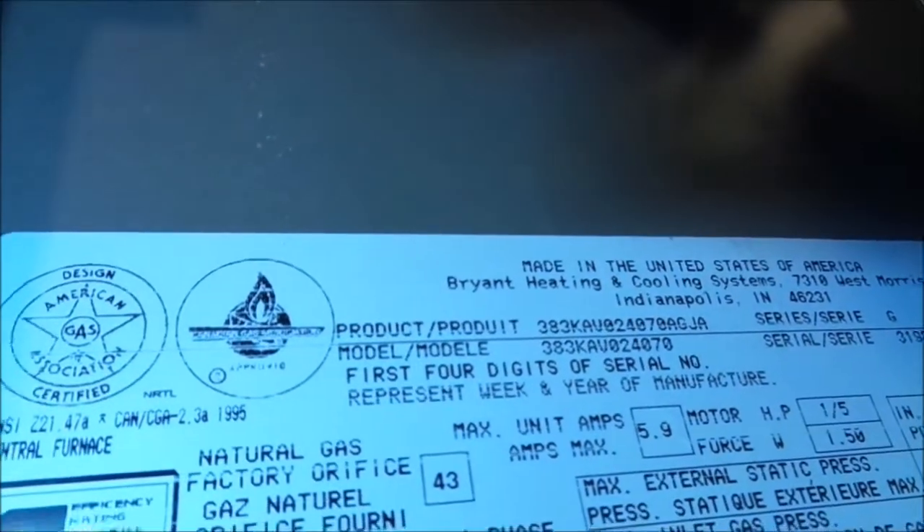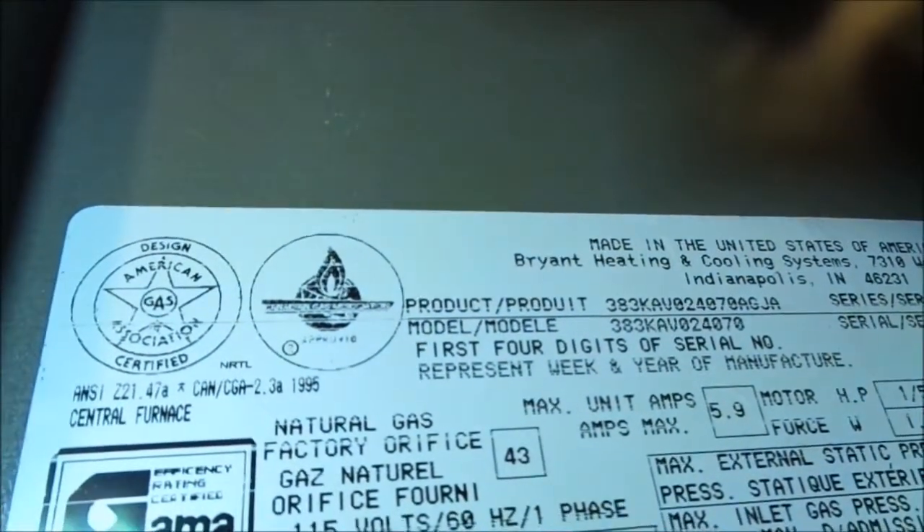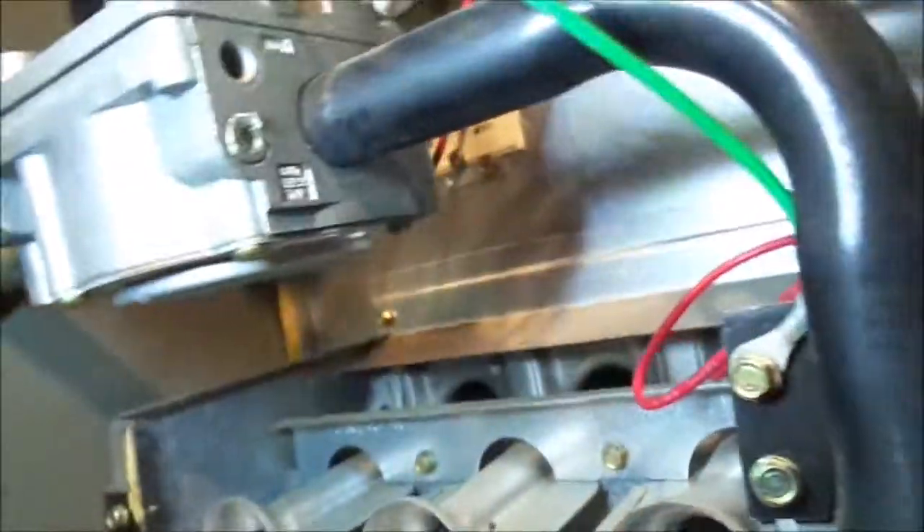I just noticed this — that light is solid on, so it's not indicating an error at this point. All I did was reset it: just unplugged it and plugged it back in, and it came on and worked fine. This is a Bryant model 383KAV024070. I'm going to clean that flame sensor and call it a day.